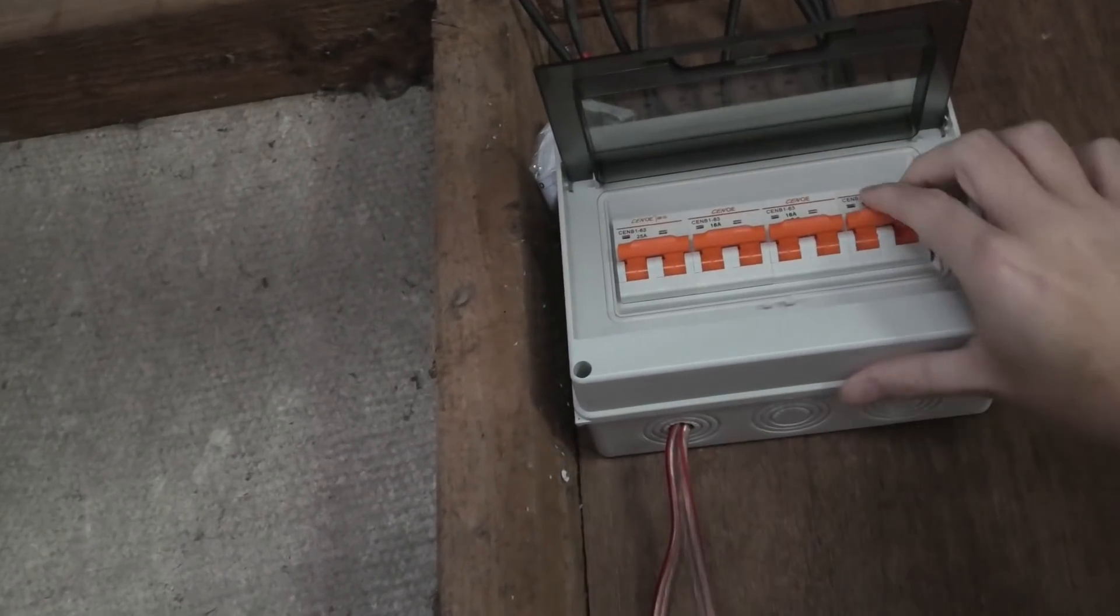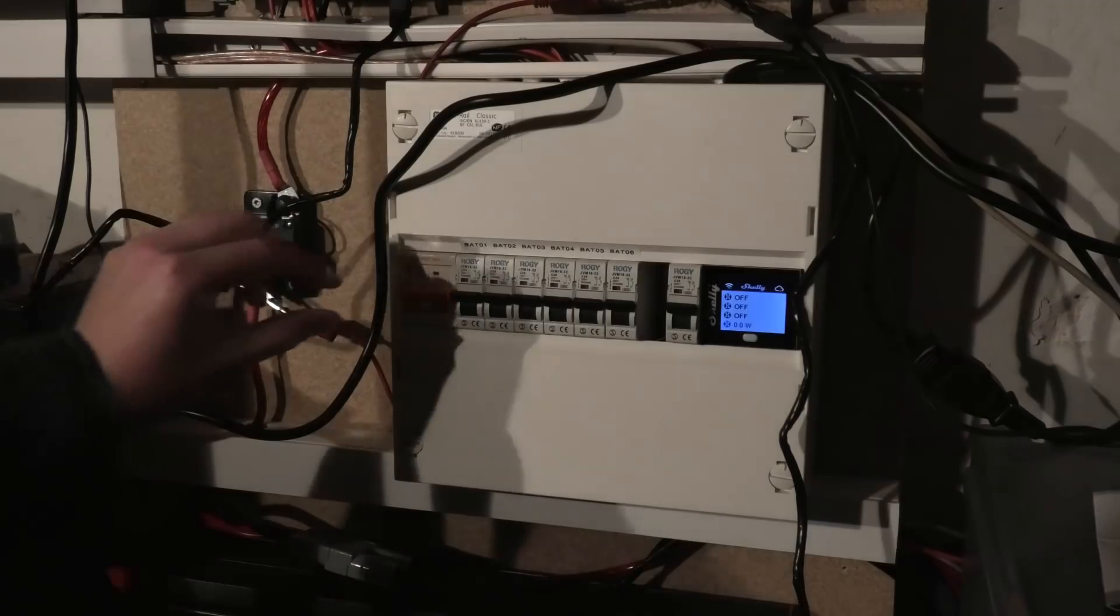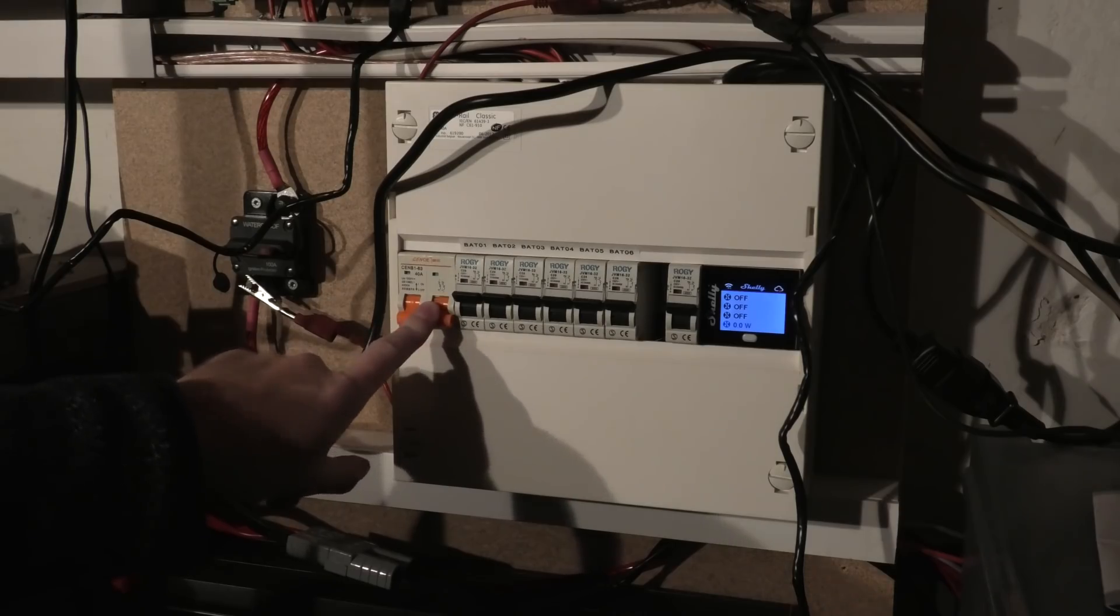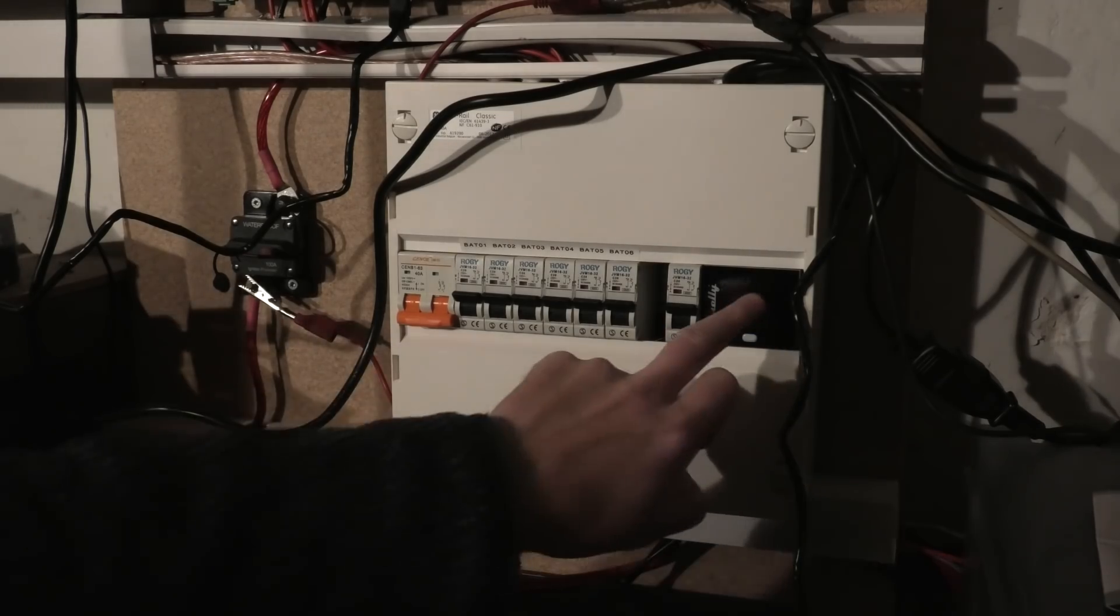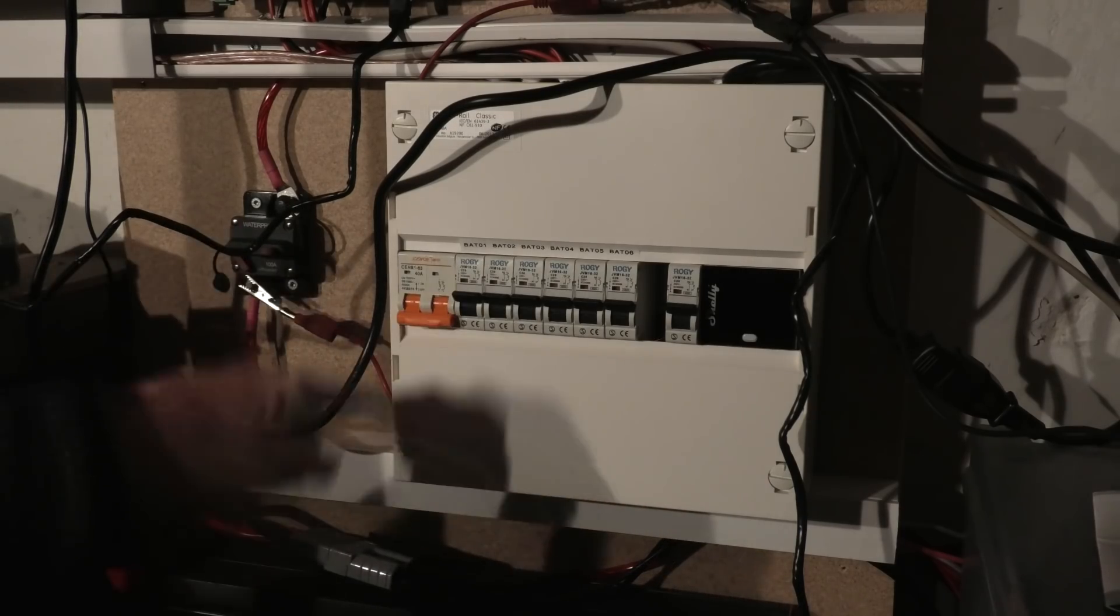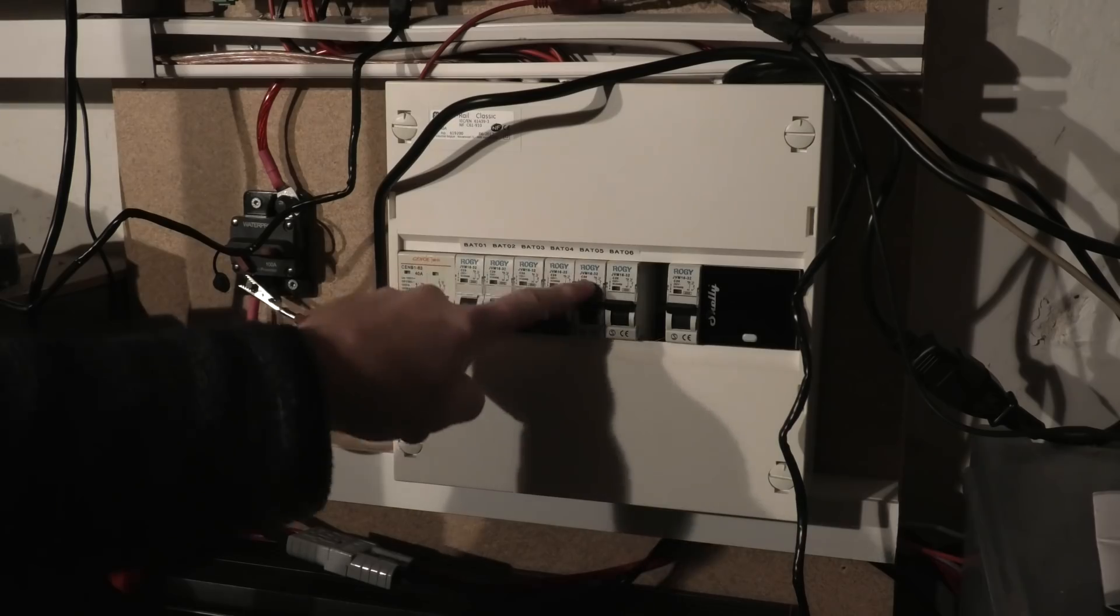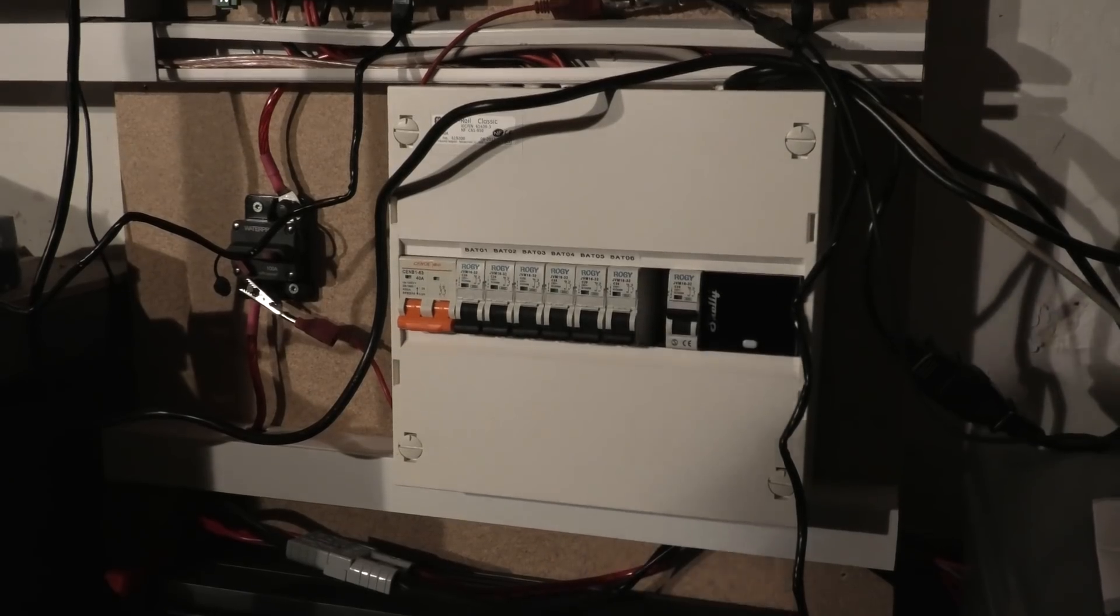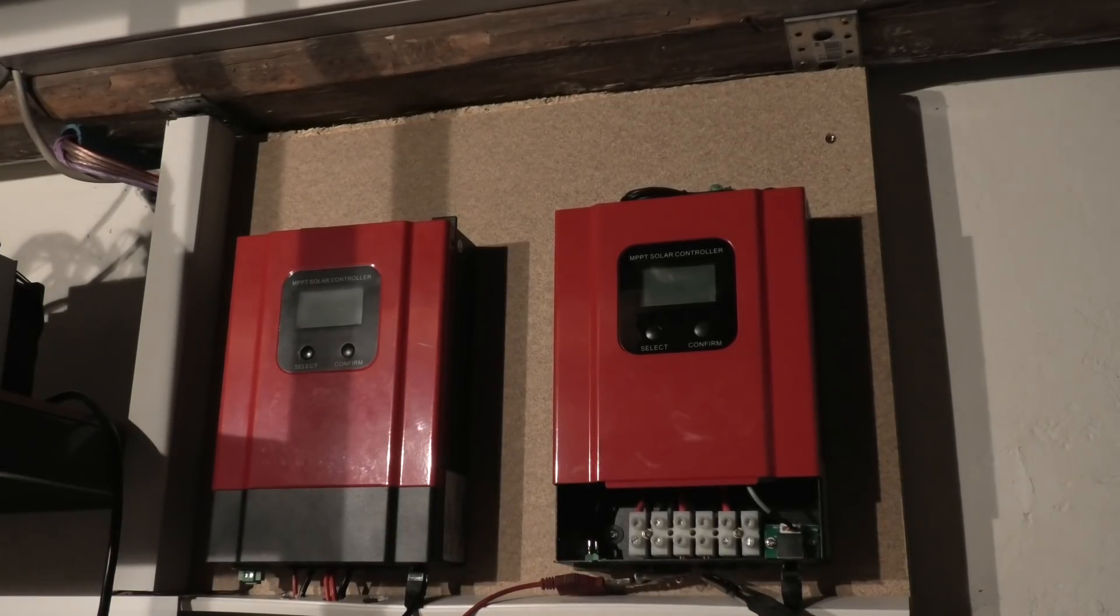So in here in the garage is where I can cut off the solar panels. There are four strings up there. We're just gonna cut all of them. I do also have this cut off which cuts off all the solar panels at once and I will cut power to the inverter as well. Turn it off down there. That turned off this unit. I'm going to take the fuse over here. That cuts power down to the inverter and then I'm gonna disconnect the battery banks one at a time. I'm gonna go get a meter and make sure that I am well, I definitely don't have power up to this unit otherwise that would be on.